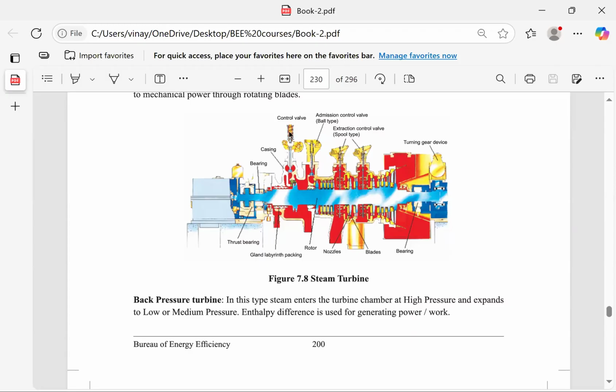This means the steam, at high pressure and temperature, expands up to this point where the parameters are negative pressure and the temperature is as low as 45 to 55 degrees centigrade. Whereas here the temperatures are, say, 150 kg pressure, temperature is say 250 to 300 degrees centigrade. When the steam reaches this parameter, it is exhausted into the condenser, cooled down, and the water is again sent to the boiler.